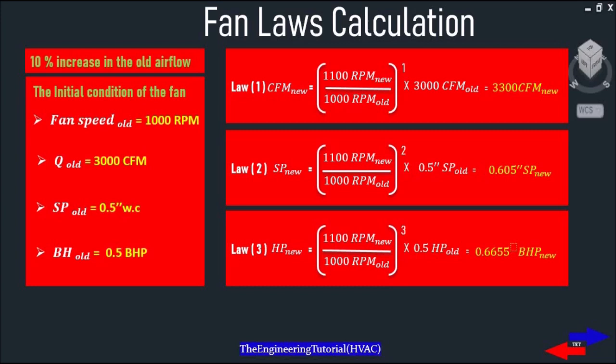The best way to understand what's happening when we change the speed of the fan is by looking at some examples. Let's say we have a fan operating at 1000 RPM, delivering 3000 CFM of air at a static pressure of 0.5 inches of water column, and has a brake horsepower of 0.5. If you speed the fan up 10% to 1100 RPM, what is the performance of the fan at the new speed?